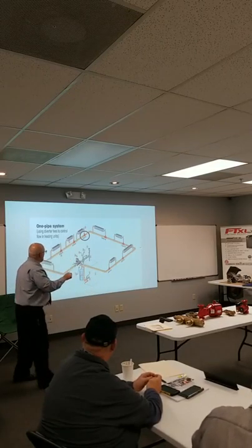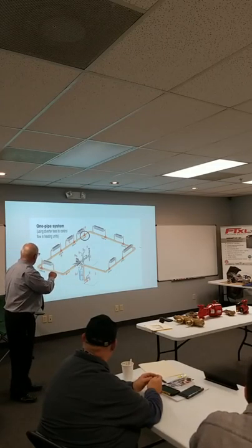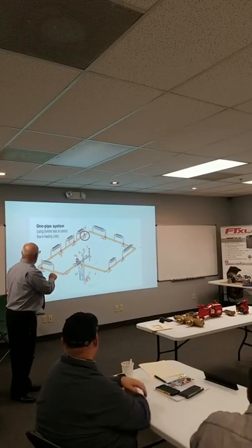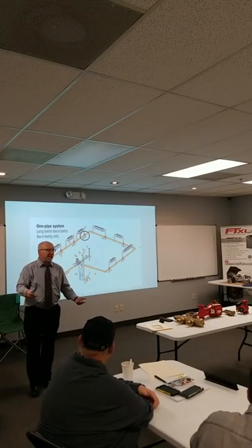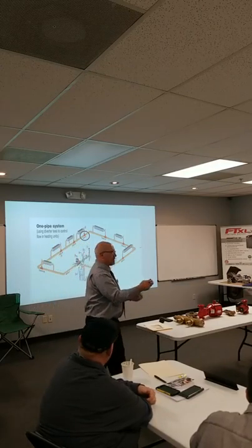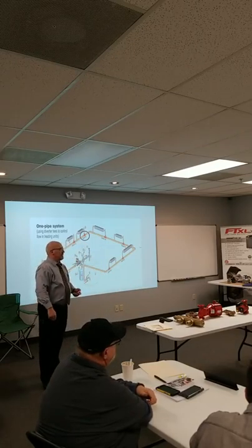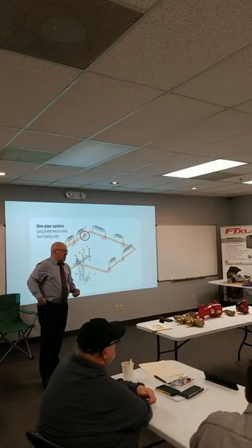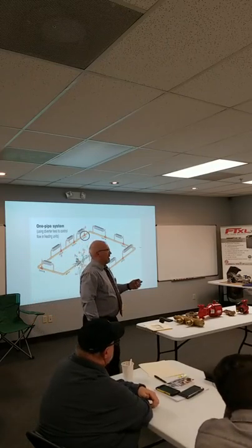But anyway, water wants to flow to the path of least resistance. So by creating this resistance, we push the water up and we circulate through the thing. Kind of pretty neat, I think. It doesn't look like a lot, but it's enough resistance to slow that water down and force it up into the radiation, until an untrained plumber fixes the leak by going out to Home Depot and putting in a regular tee. The rest of the house works, but that room remains cold.